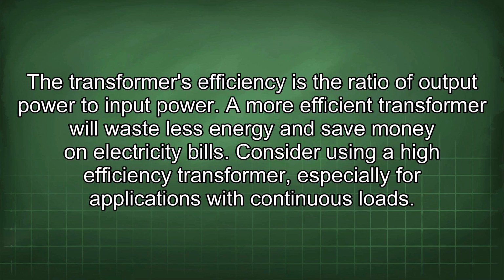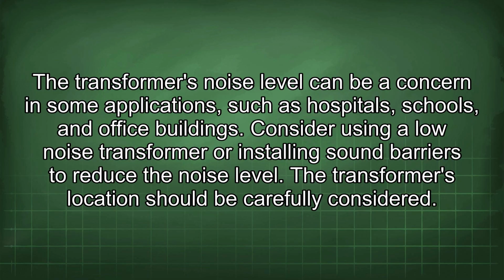A more efficient transformer will waste less energy and save money on electricity bills. Consider using a high-efficiency transformer, especially for applications with continuous loads. The transformer's noise level can be a concern in some applications, such as hospitals, schools, and office buildings. Consider using a low-noise transformer or installing sound barriers to reduce the noise level.